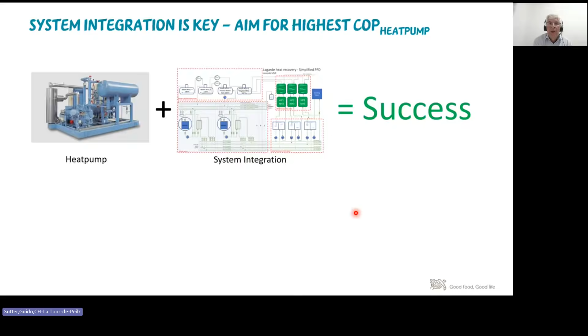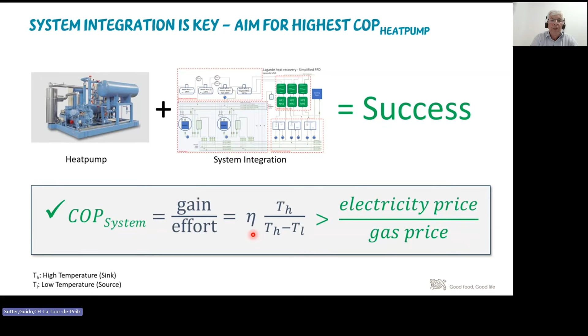The COP of the system, which is the gain over the effort, with some temperatures, high temperatures, and the temperature difference, and some efficiency factors for the compression, for the compressor. We have to fulfill the condition that this COP of the system is higher than the electricity price over the gas price. So this electricity gas price ratio always needs to be lower than the COP of the system. COP has to be higher than this ratio.